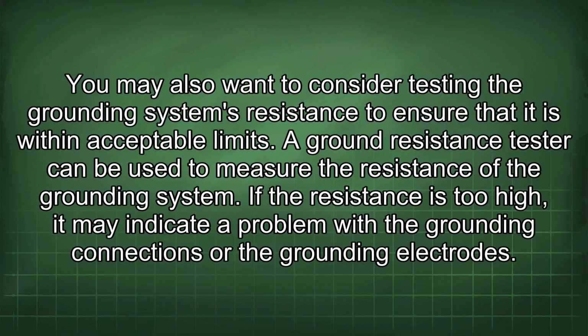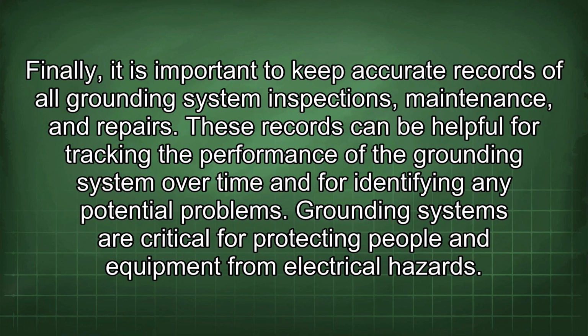You may also want to consider testing the grounding system's resistance to ensure that it is within acceptable limits. A ground resistance tester can be used to measure the resistance of the grounding system. If the resistance is too high, it may indicate a problem with the grounding connections or the grounding electrodes. Finally, it is important to keep accurate records of all grounding system inspections, maintenance, and repairs. These records can be helpful for tracking the performance of the grounding system over time and for identifying any potential problems.